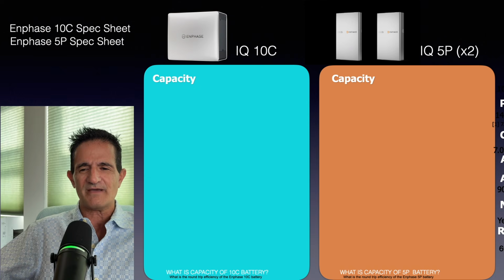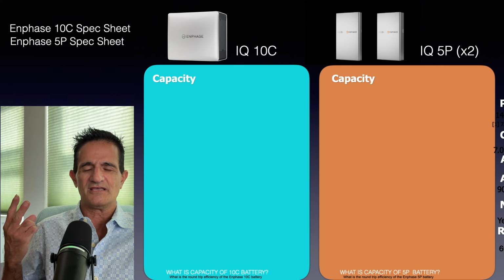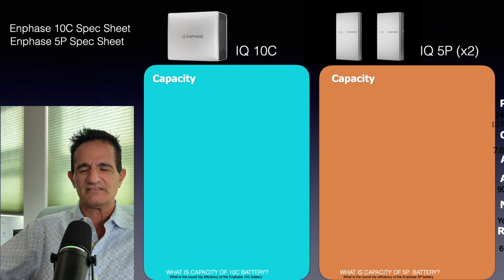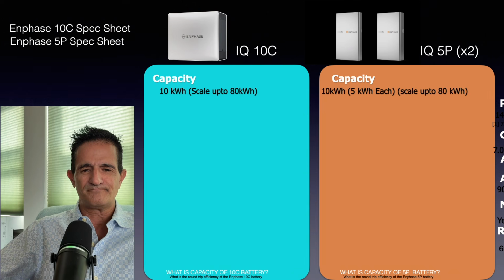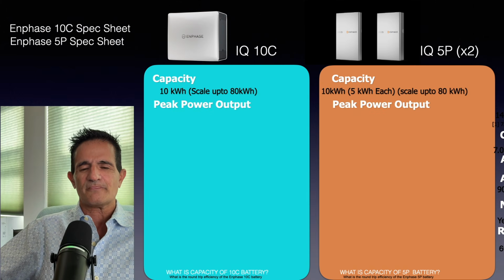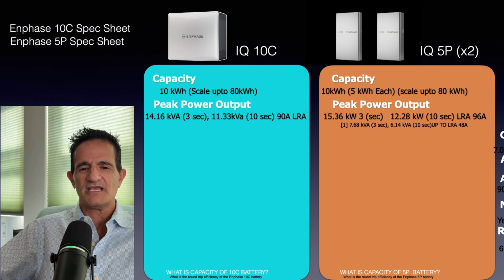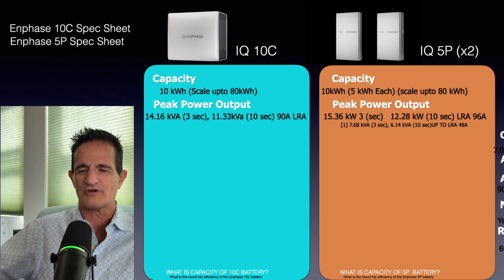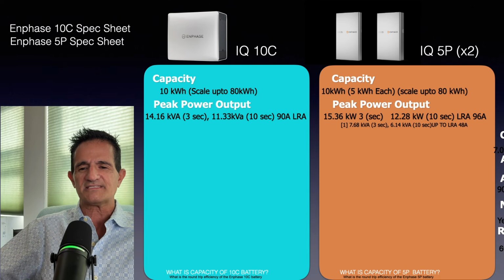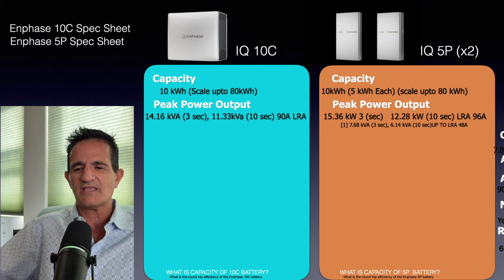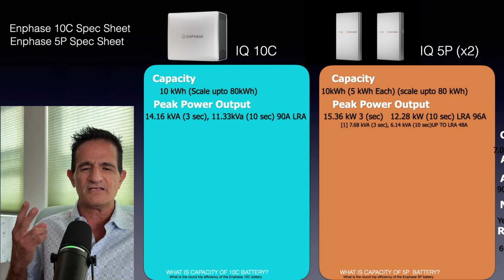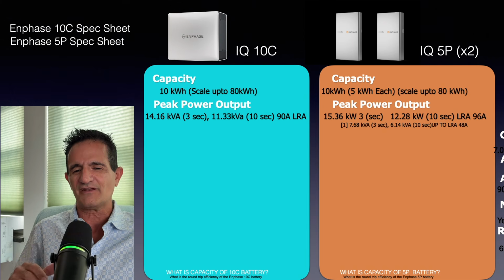So now let's talk about some other specs. The capacity. In this case, by the way, I'm going to compare two IQ 5P batteries, so we're comparing apples to apples. So in both cases, 10 kilowatt hours if you have two IQ 5P batteries, and you could scale it up to 80 kilowatt hours. The peak power output is 14.16 kVA for 3 seconds, 11.33 kVA for 10 seconds, and 90 amps LRA. This is to run air conditioners or heat pumps. I'll talk about that more in a minute. Versus 15.36 kVA for 3 seconds on the IQ 5P, and 12.28 kVA for 10 seconds, and LRA of 96 amps. Actually, the two 5Ps are slightly better performance, but I don't think this is earth-changing, by the way.